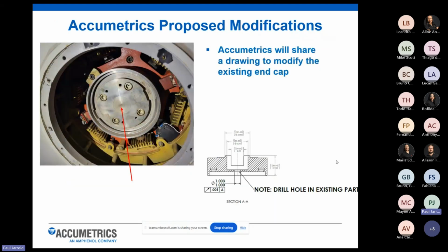So on the end of the brushless exciter for these smaller gas turbine generators, when you remove the cover plate, you will see a piece that they call the rotor end cap. This is the only part of the machine that needs to be modified to house our rotating transmitter, and we will provide drawings and information on how to modify this.